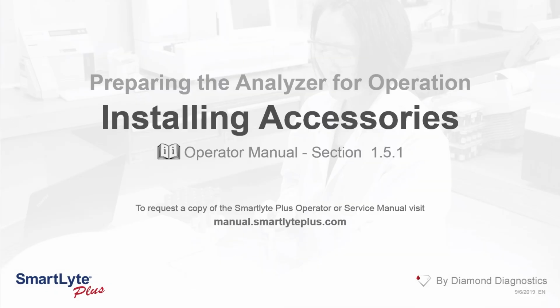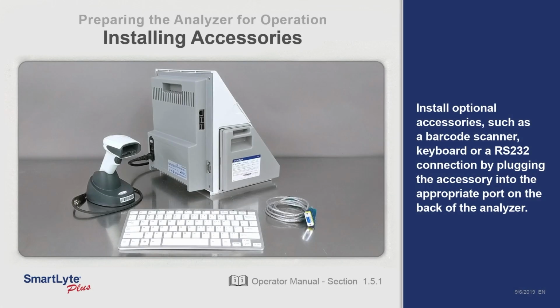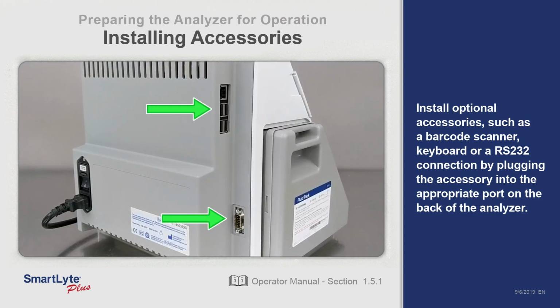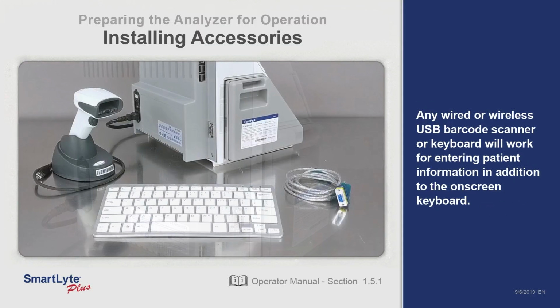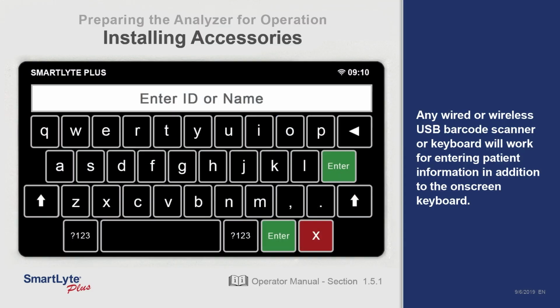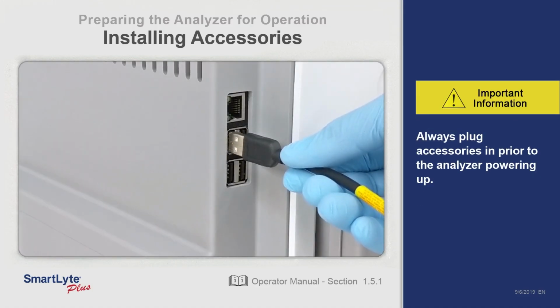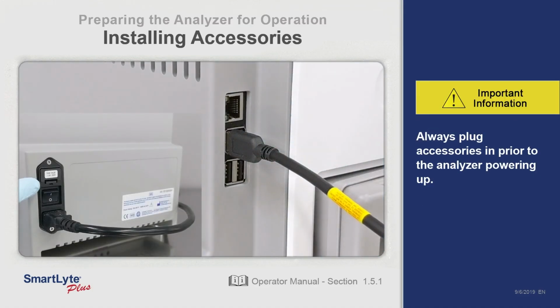On the SmartLyte Plus, install optional accessories such as a barcode scanner, keyboard, or RS-232 connection by plugging the accessory into the appropriate port on the back of the analyzer. Any wired or wireless USB barcode scanner or keyboard will work for entering patient information in addition to the on-screen keyboard. Always plug accessories in prior to the analyzer powering up.